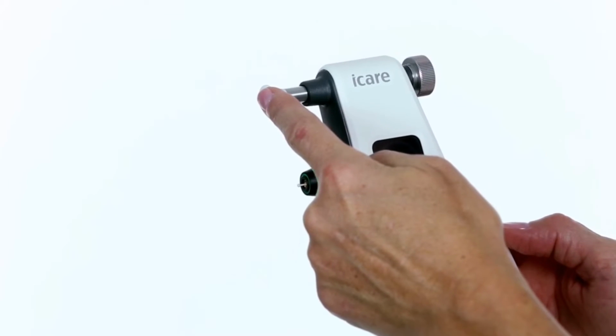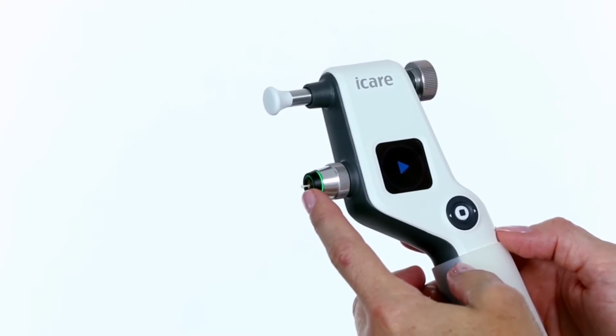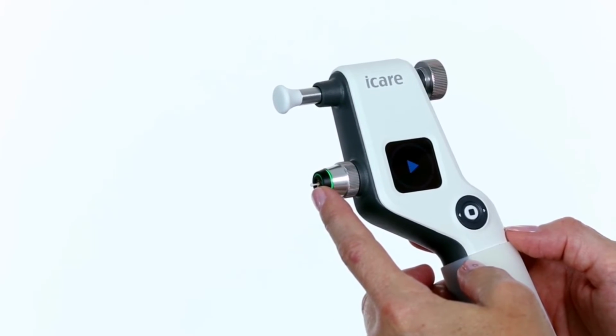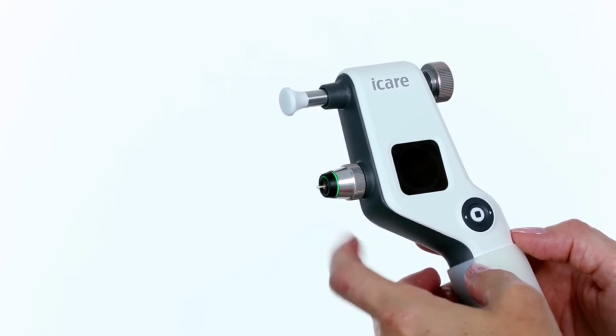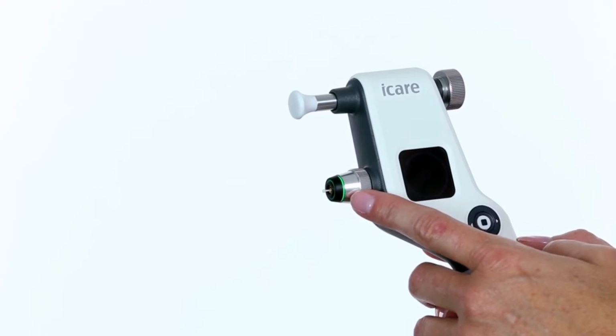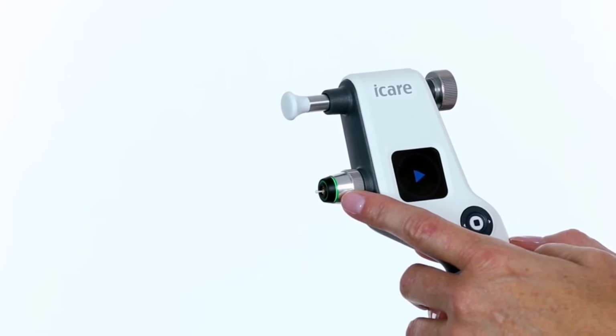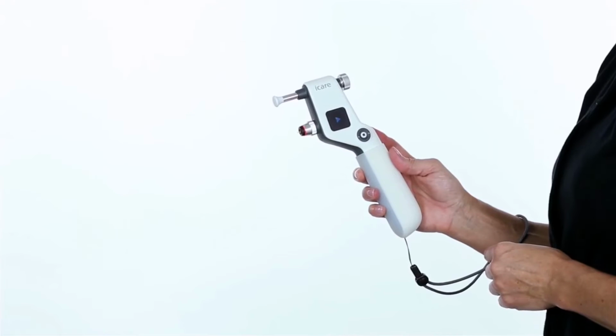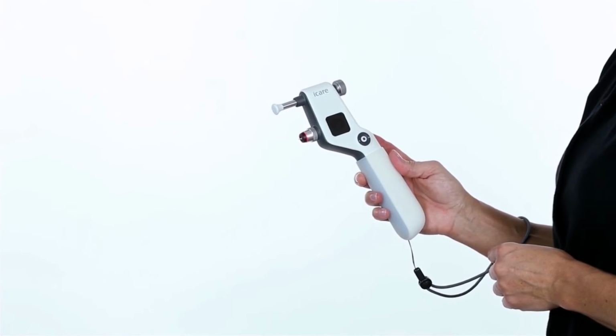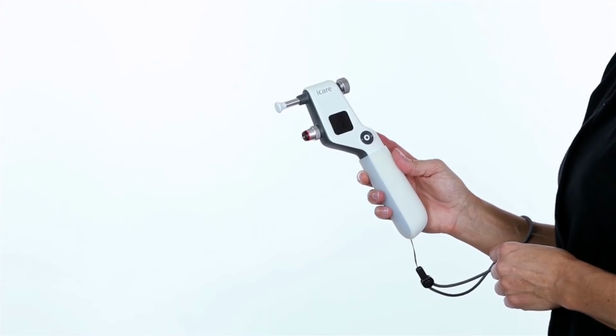Place the forehead support on the patient's forehead. Aim the probe in the center of the eye, and the distance of the probe to the cornea should be 4 to 8 millimeters. The green probe base light indicates proper alignment. If the probe base light is red, the alignment is incorrect.